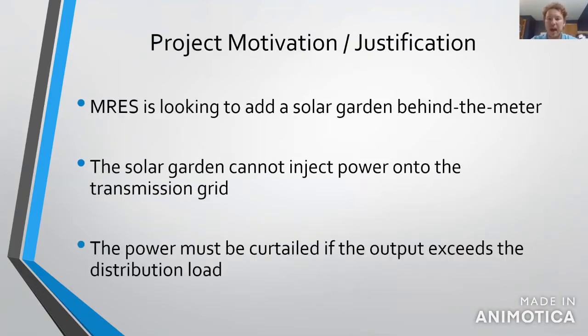Missouri River is looking to add a solar garden behind the distribution meter at one of their member communities. There are a few reasons it would be placed on the distribution side: it's cheaper, and it can be implemented much faster than if integrated on the transmission side. The primary concern is that it cannot inject power back on the transmission grid due to regulations. Therefore, the output of the solar garden cannot exceed the load on the distribution system, and if this were to happen, the output must be curtailed.